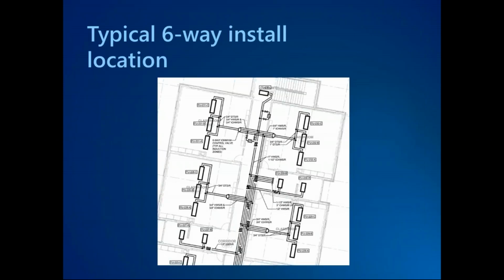So a basic layout for something you might see in a school is having your 4-pipe mains in the hallway with 6-way control valves placed as close to those mains as possible. And then you have your dual temperature piping going from your 6-way to each individual zone, each set of chilled beams. Things to take note of here, and what is common with almost all of the piping layouts you're going to see, is that the run-out piping to the 6-way and the piping coming off of the 6-way are parallel to one another. They're all going in the same orientation.